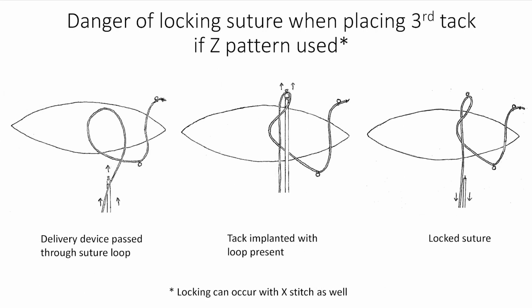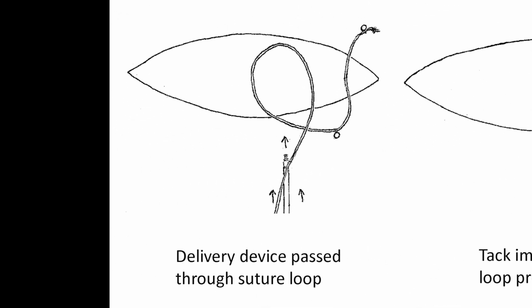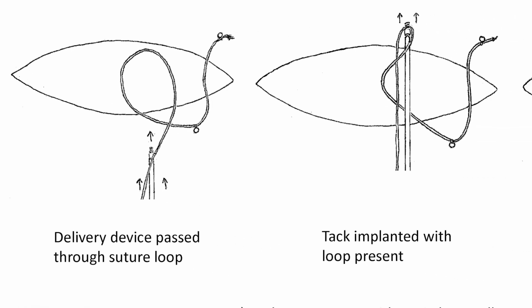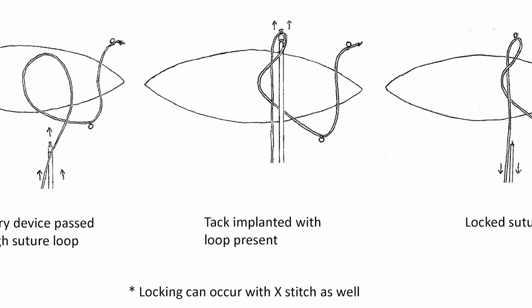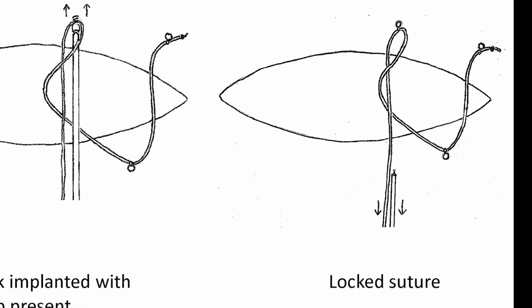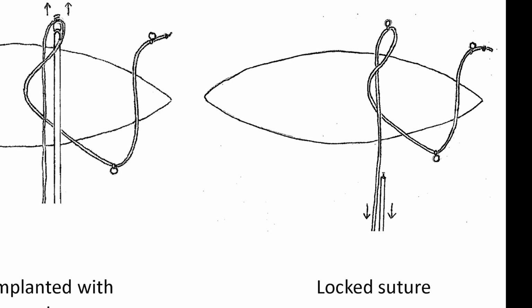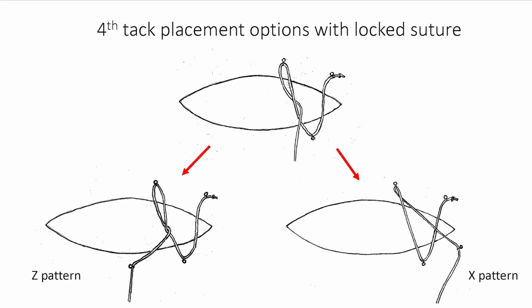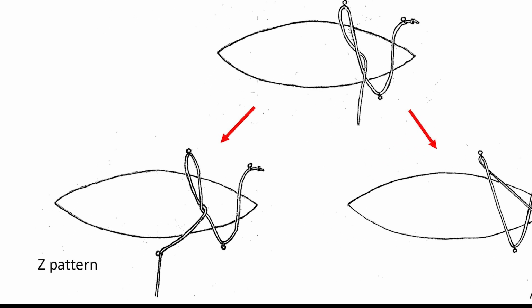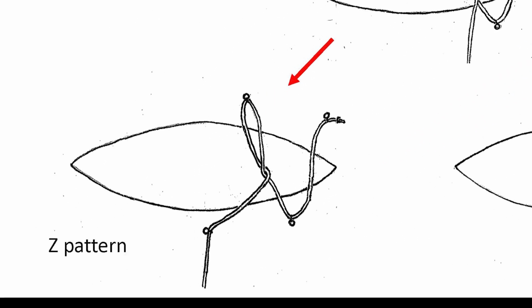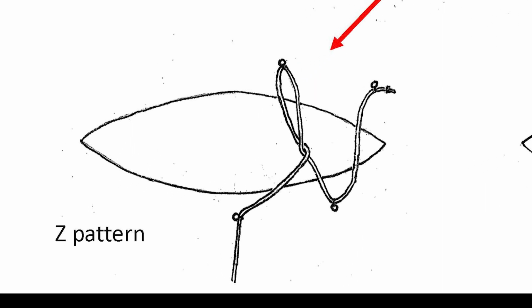Here we see the delivery device being passed through a fully formed loop prior to implantation of the 3rd tack. This results in the suture becoming trapped or locked beneath the suture joining tacks 2 and 3. Short of removing the 3rd tack, which is not an option, there is no way to unlock the suture. If the 4th tack is placed so as to complete the Z pattern, the lock will significantly impede the closure.